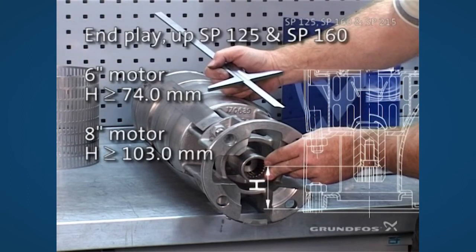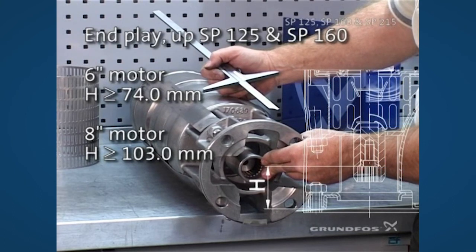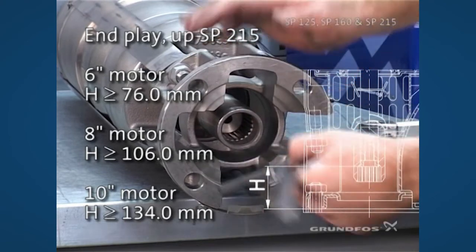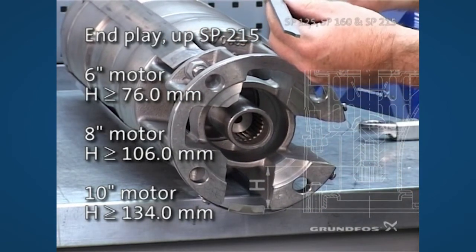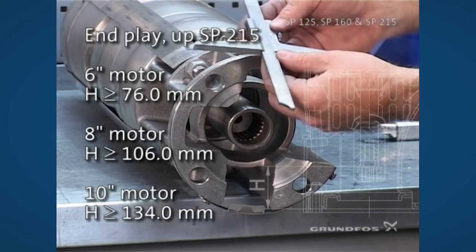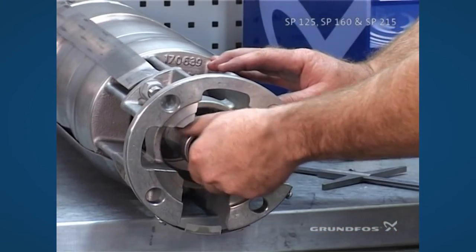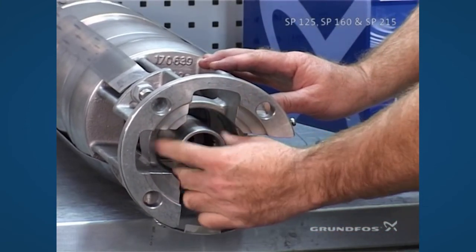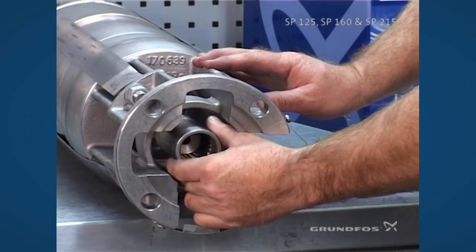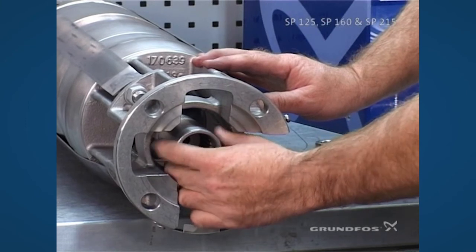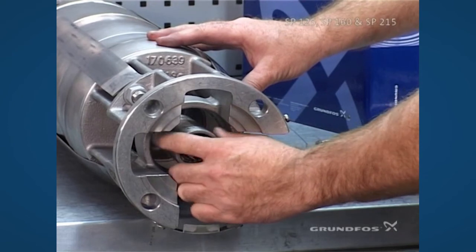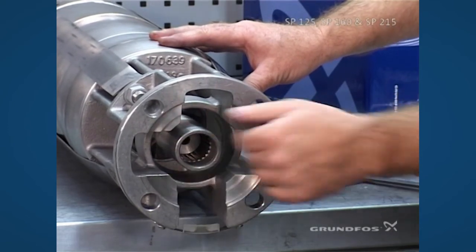Then simply push the shaft upward and take the up travel in the unit. Re-secure the screw and remove your depth vernier. Here the minimum up is 103. Now we can check our rotation. On the smaller units you can do this by hand. On the larger units it may require a specialty tool made out of an old shaft with a handle on it. You want to make sure that there are no metal to metal noises while you're rotating it. We have good rotation at this point.